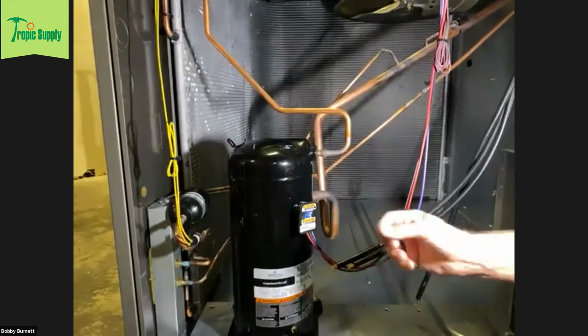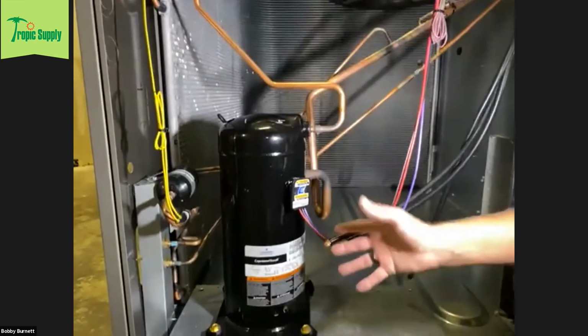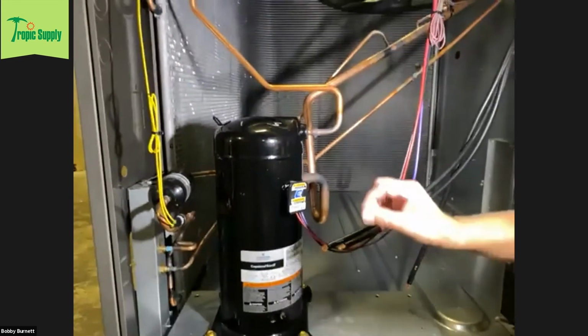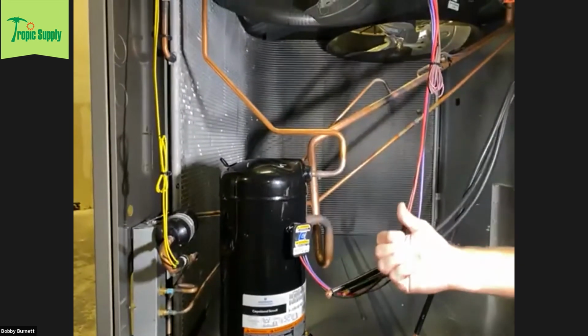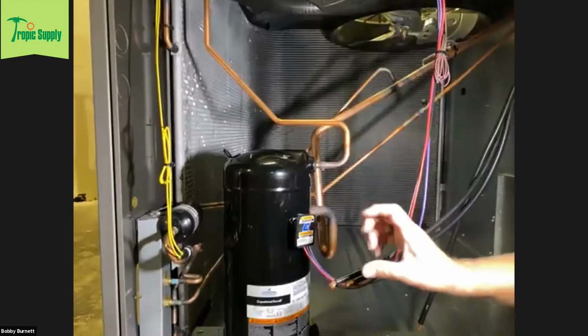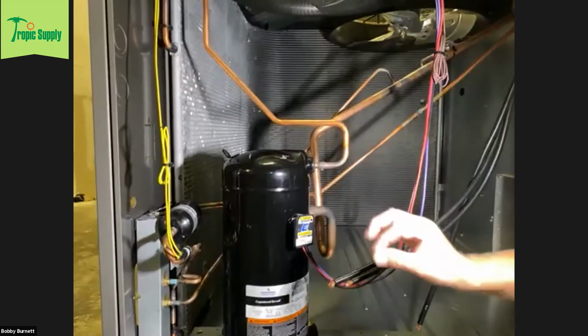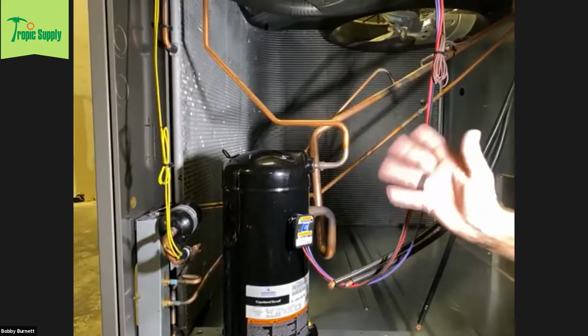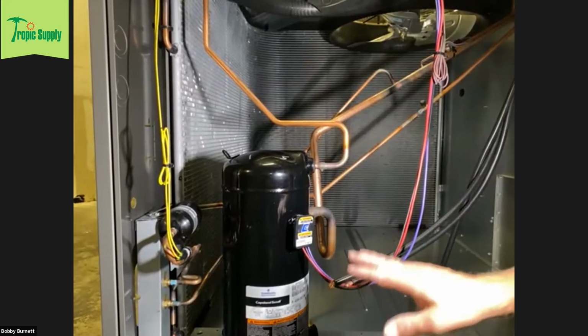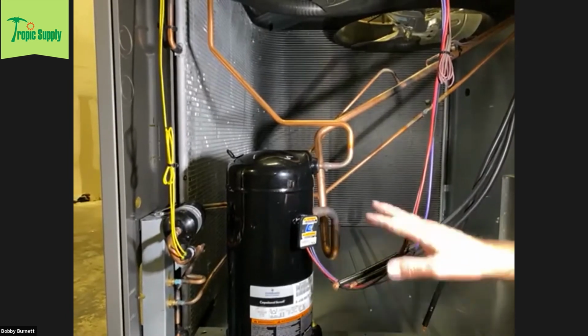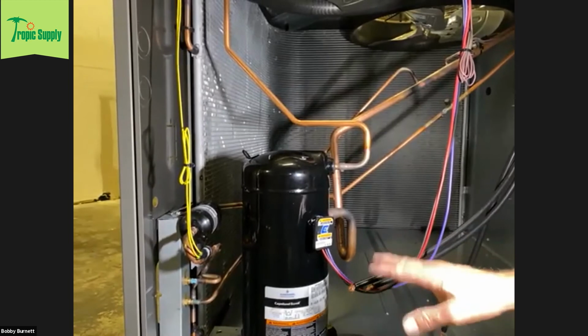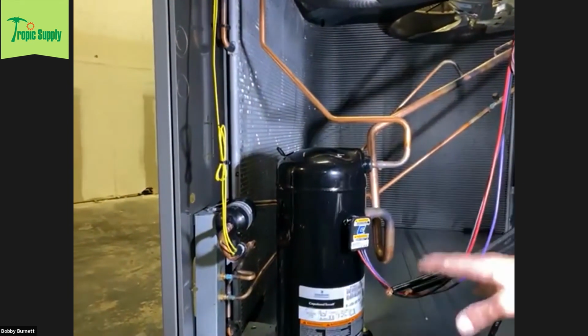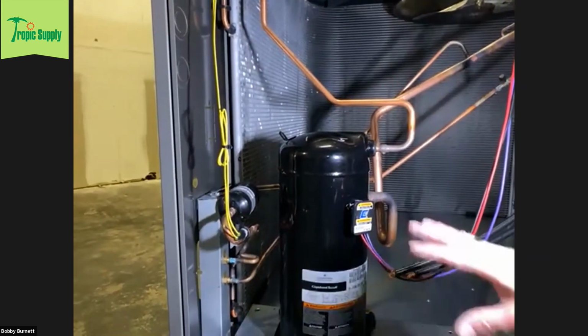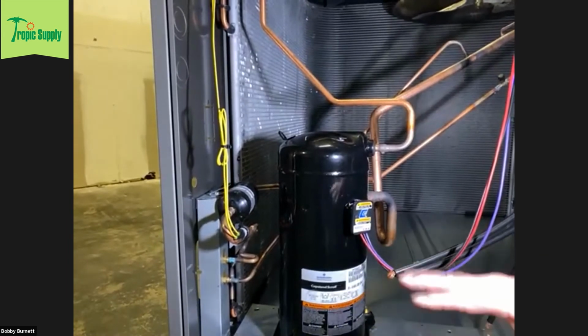Because sometimes with forklifting these units you can get damage to the bottom row of this coil, that bottom row is inactive, just a dummy row on the bottom of these coils. So if you come across that row dented a bit from shipping, forklifting, or crane lifting it onto a roof, you don't have to worry about it, it's not an active part of the coil.